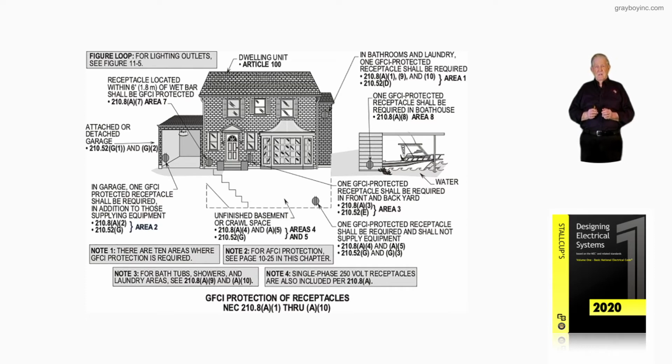The way the bathroom section has been revised, if you had the 20 amp number 12 circuit directly feeding the bathrooms, you could now tap off and maybe feed a little vent fan heater. Couldn't do that before, but now read it very carefully, because (A)(9) and (A)(10) has really been added in and revised.